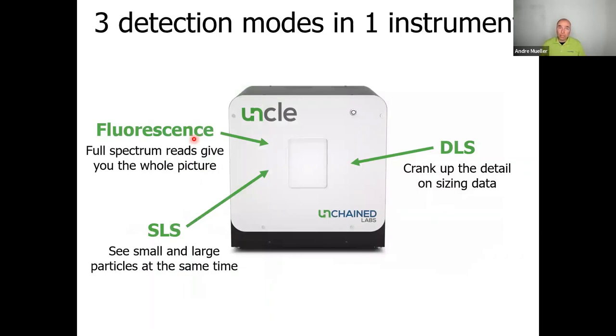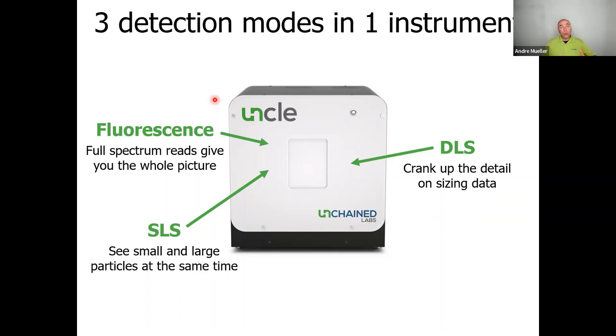UNCLE combines three distinct detection methods in one instrument. The three modes are fluorescence, static light scattering, and dynamic light scattering. In fluorescence mode, we use two laser systems: a laser at 266 nanometers and a laser at 473 nanometers — a UV laser and a blue laser — to excite fluorescence of the analytes. We read the full emission spectrum from 250 to 720 nanometers, and this flexibility keeps you in control.